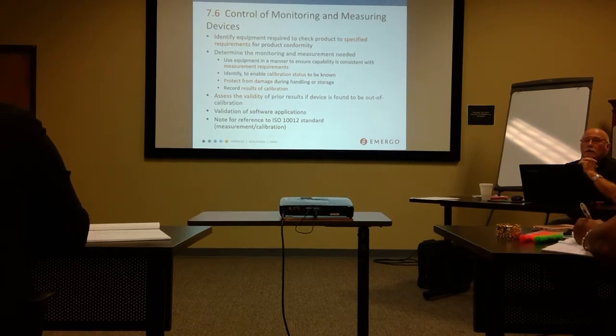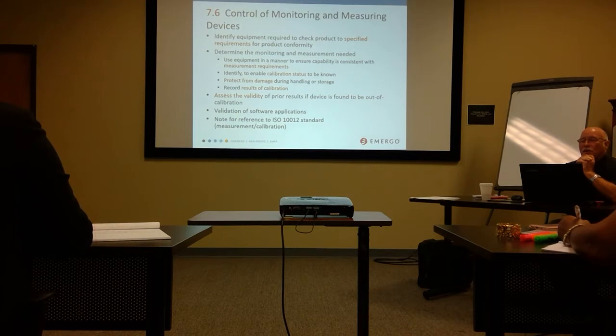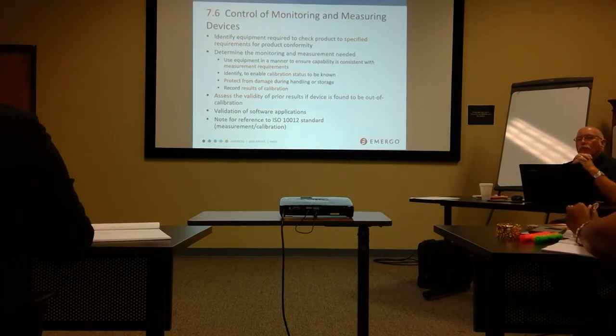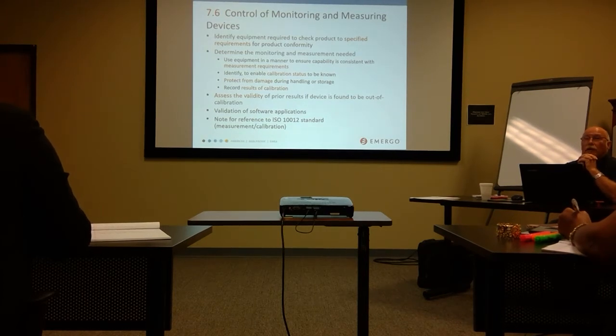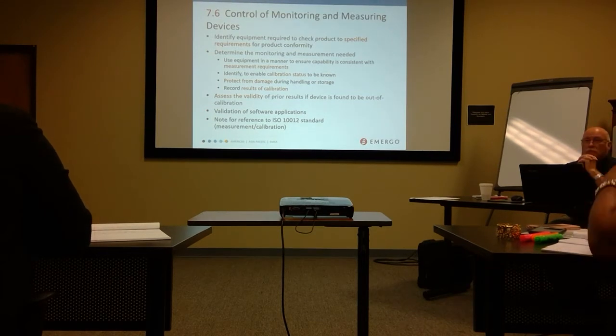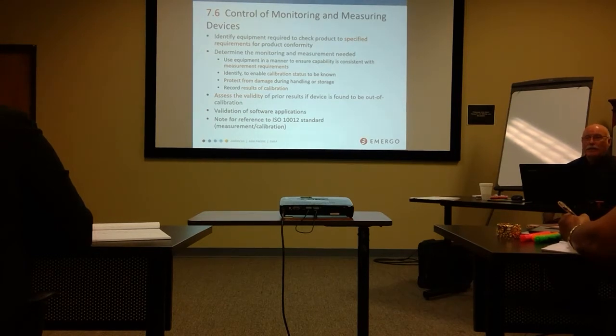Yeah. And then on the unique identification, can we just use serial number? That's perfect. Instead of putting an asset tag on it. Most finance departments will force that for their own purposes. Not everything has a serial number though. Right, if it has a serial number, that's what we use. If it doesn't have a serial number, we'll assign a number to it. That's fine. Assign it, as long as it's unique. Perfect. Doesn't matter how you do it. Serial numbers are great. Instrument number, as long as you can specifically identify that caliper, that's what we're after, or whatever else it might be.